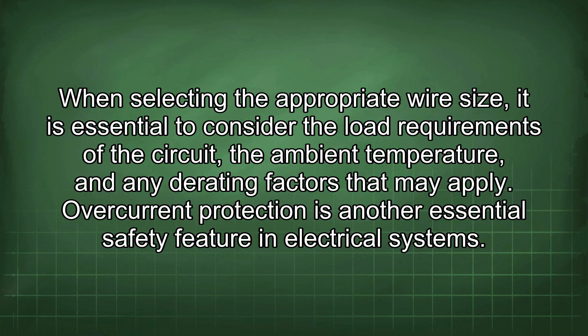Overcurrent protection is another essential safety feature in electrical systems. Overcurrent protective devices, such as circuit breakers and fuses, are designed to protect conductors and equipment from overloads and short circuits. The NEC requires that overcurrent protective devices be selected and installed in accordance with their interrupting rating and ampacity rating.